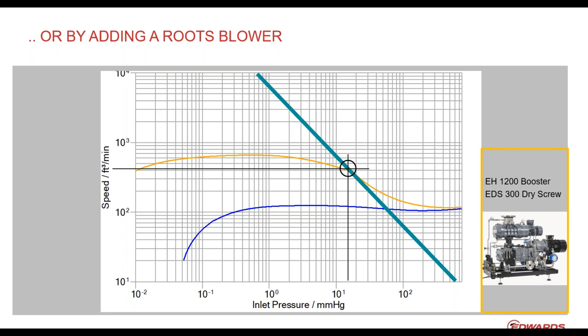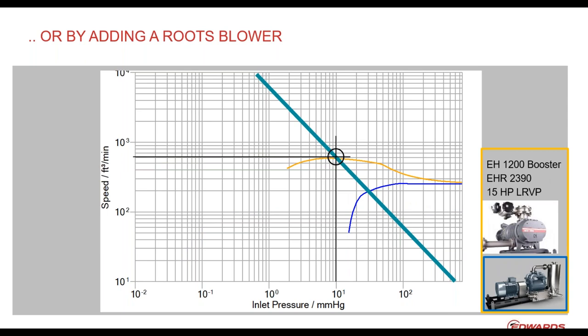In many cases it makes a lot of sense to move into a system instead of just putting in a bigger pump. The mass flow is handled fine by everything under the pump curve. The blower only kicks in when it develops the capacity you need at lower pressure. A blower on top of a liquid ring pump can even get to a pressure — say 10 Torr — that a liquid ring pump alone could not reach due to its operating principle.